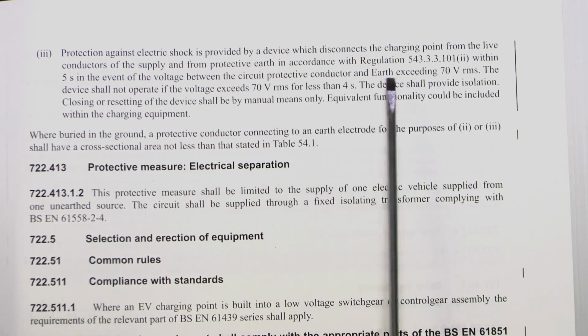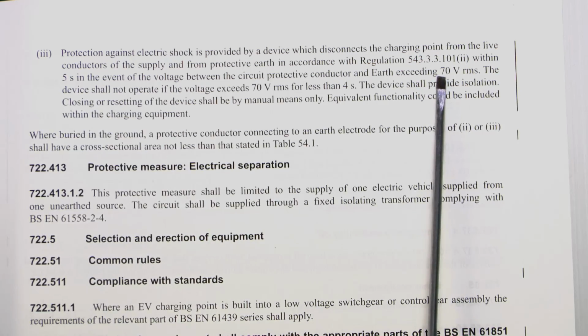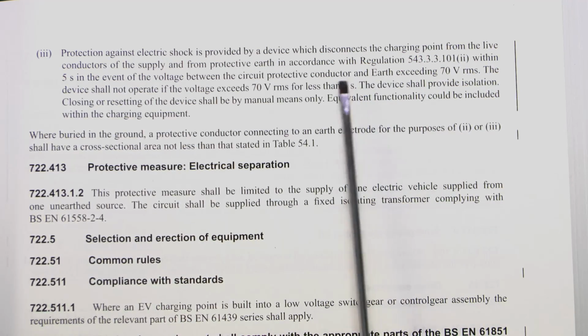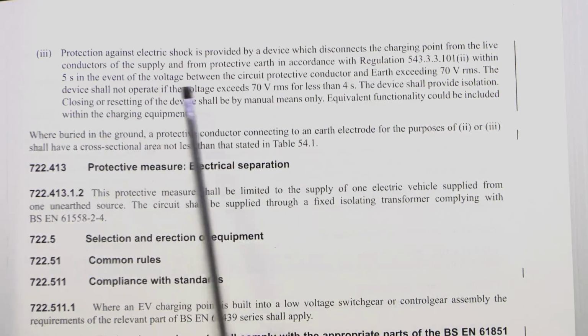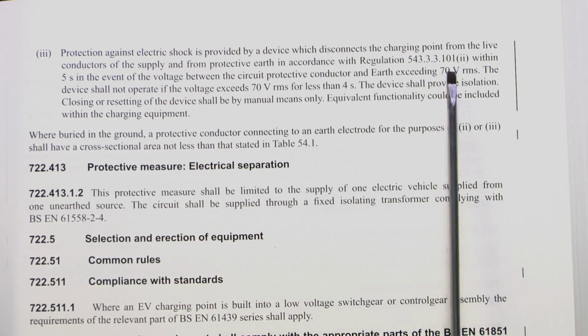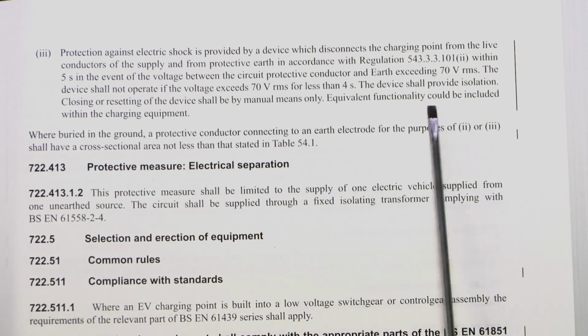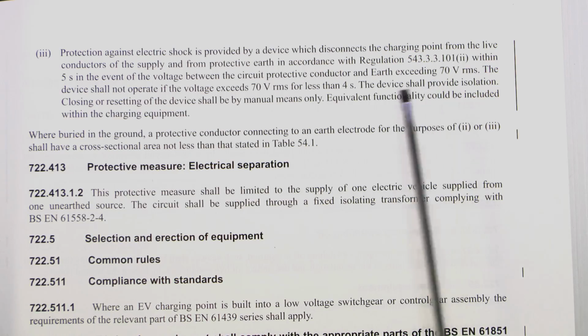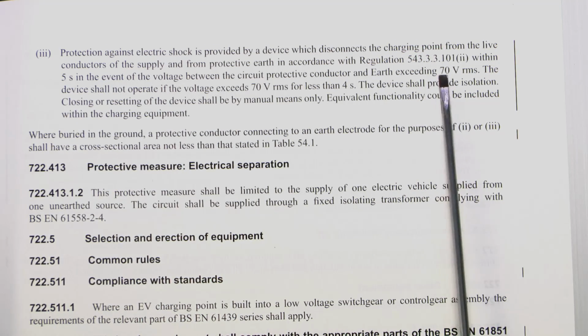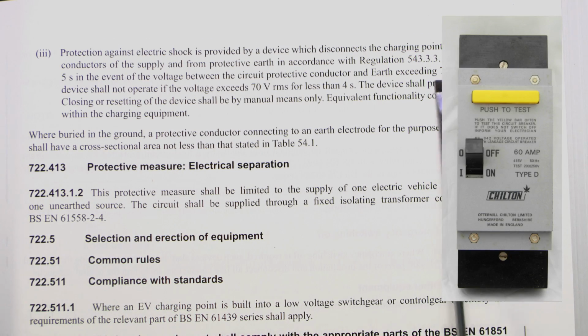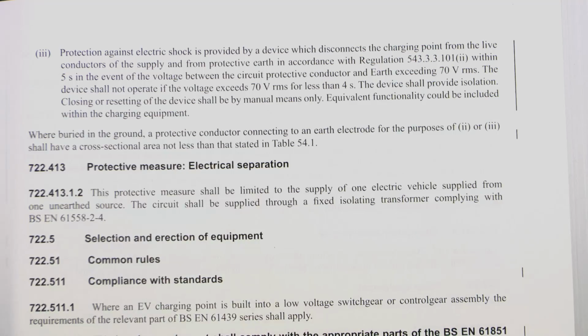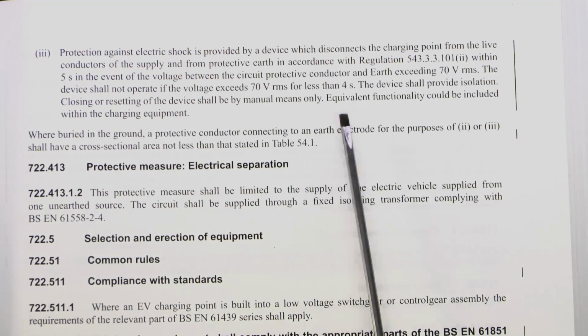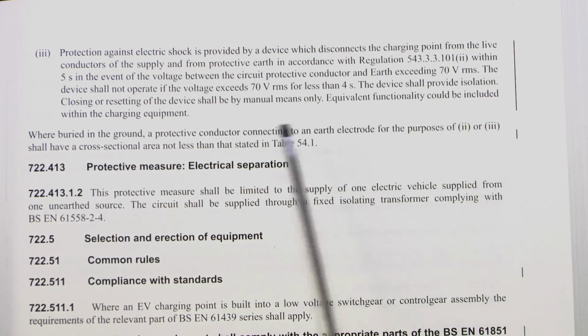So essentially you need a device which detects a voltage between the actual ground itself, as in the soil or whatever outside, and the protected conductor, and then if it gets over 70 volts it disconnects. If this sounds a familiar device, then it is, because this is basically what the old earth leakage circuit breakers used to do, which were deleted in the early 1980s, though they were slightly different, but the principles are quite similar. And the important bit here is equivalent functionality could be included in the charging equipment.